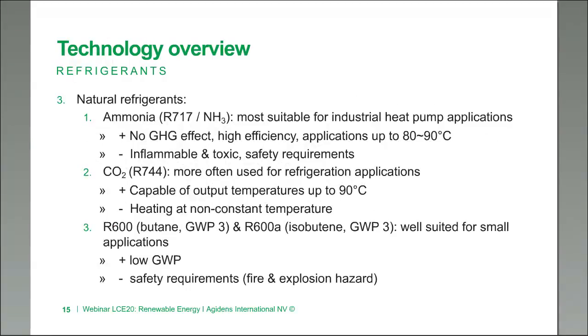Looking at the different kinds of refrigerants, we have natural ones like ammonia, R717 or NH3. This is the type of refrigerant most suitable for industrial heat pump applications. The positive points are the lack of greenhouse gas effect, high efficiency, and the fact that ammonia supports applications up to 80 or even 90 degrees centigrade. The disadvantage is that it's flammable and toxic, so you will face certain safety requirements. However, ammonia stinks terribly, so if there is a leak, you tend to know it very quickly and can evacuate before it actually hurts you.